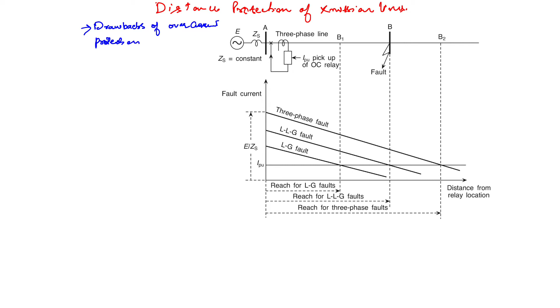So we can say that the relay may underreach or overreach depending upon the type of fault. This is not a desirable trait for a protection system. First, we considered the different types of faults. Now, from this diagram, you will see that if the overcurrent relay pickup setting is equal to I pickup, then it gives the reach up to the bus B, assuming the source impedance remains constant.